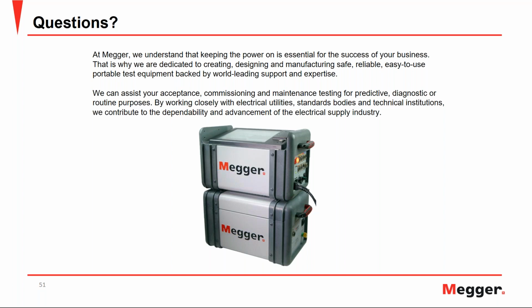And when you have a high ground resistance, be it from the neutral to the ground, I would assume that you would run into a different problem than a high power factor value, because then the amount of current going through the ground would be limited, and that may cause a different problem, but not high power factor. But again, high power factor can be caused because of grounding issues, and a single point ground system is the way to go.